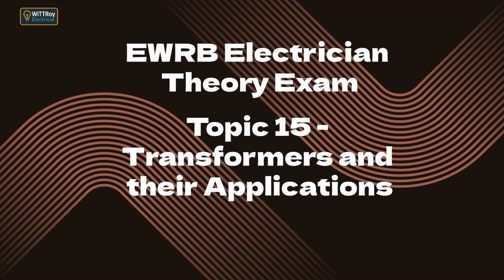15.1f. Explain that the kVA rating of a transformer is limited by the temperature of the core and windings. A transformer's kVA rating is limited by how hot the core and windings can safely become. If the transformer carries too much load, heating increases and insulation can break down. Overheating reduces life expectancy and may cause internal faults. The rated kVAR ensures the transformer operates within safe temperature limits. This is why cooling systems, oil, radiators, fans are important.